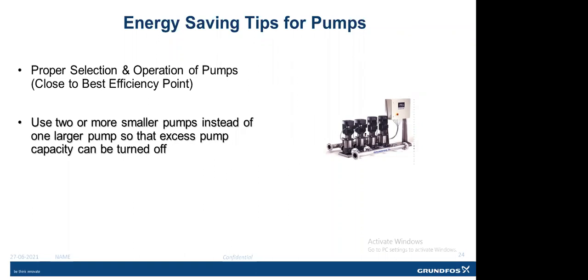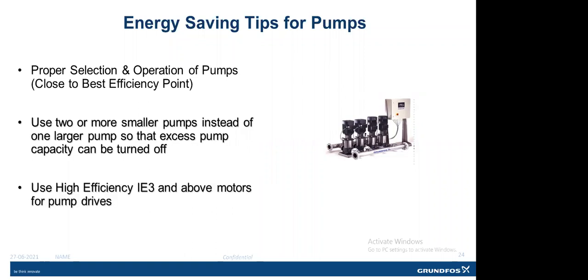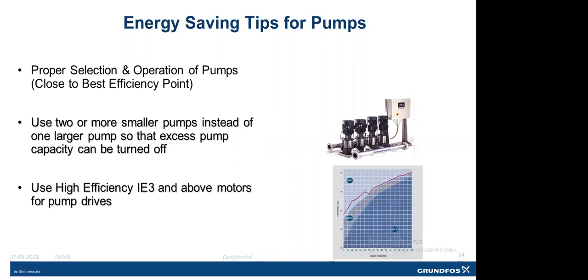So if we use only one pump at higher flow as well as lower flow, as we've seen at the pump curve, if you operate the pump at lower flow, the efficiency will drop down. So instead, check whether we can design the pumps according to the requirement by installing smaller capacity pumps based on your requirement: minimum, moderate, and maximum. We can save a lot in the pumping system and use high efficiency IE3 and above motors for pump drives. Now we have come up with IE5 technology motors as well, that we will discuss separately in the next session, which will be covered by my colleague Frederick.